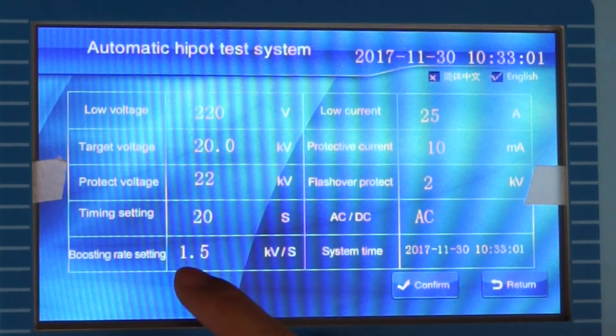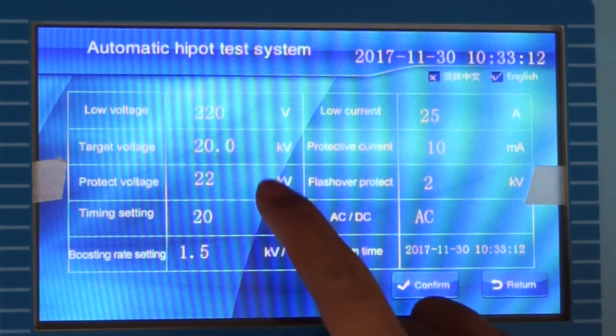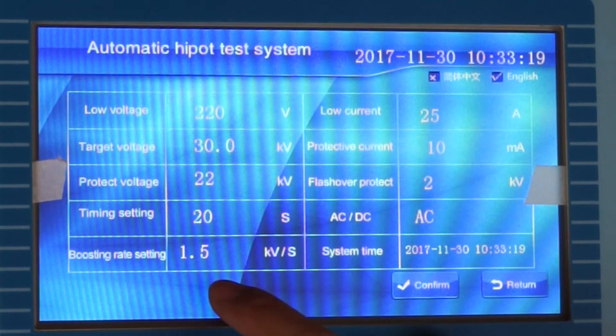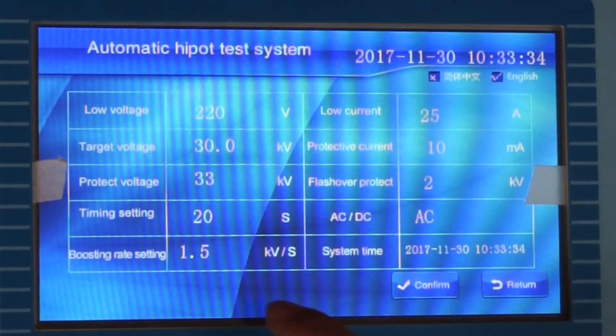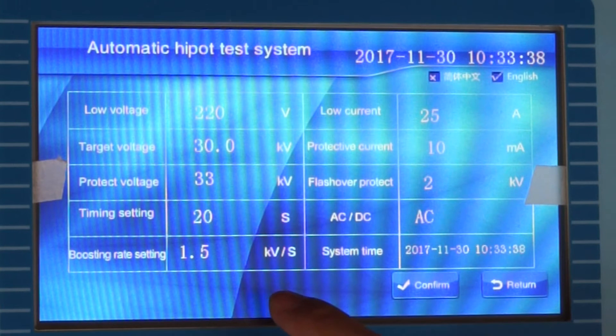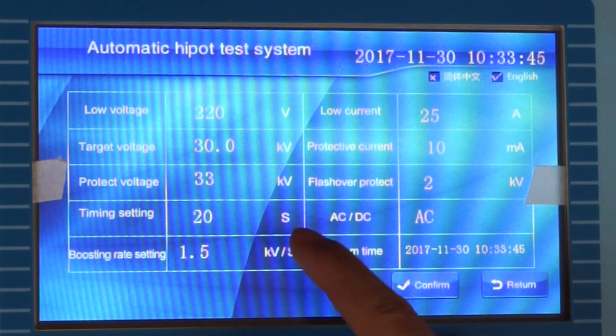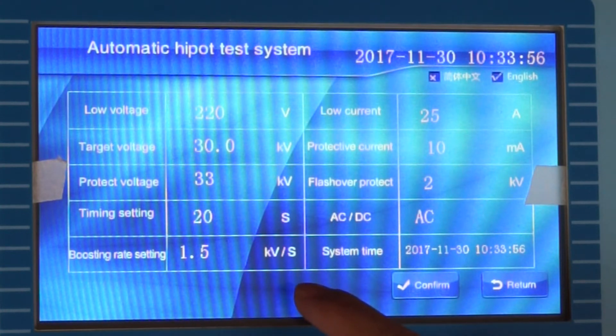Low voltage is usually set to 1.1 times the low voltage. Target voltage is the target value voltage — we set 30 kV. Protect voltage is the protection action value — we set 33 kV, usually 1.1 times the target voltage. Timing setting is the withstand test time — we set 20 seconds. Boosting rate setting — we set 1.5 kV/s.